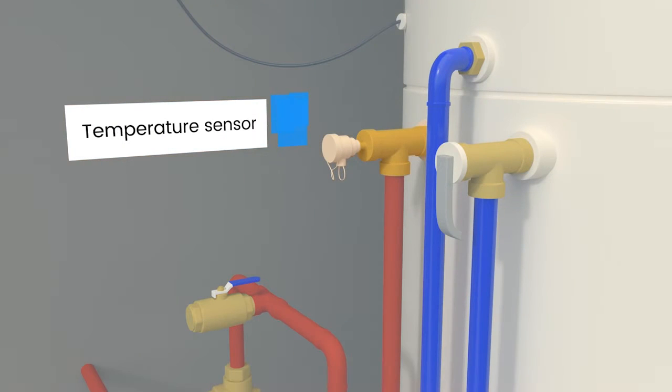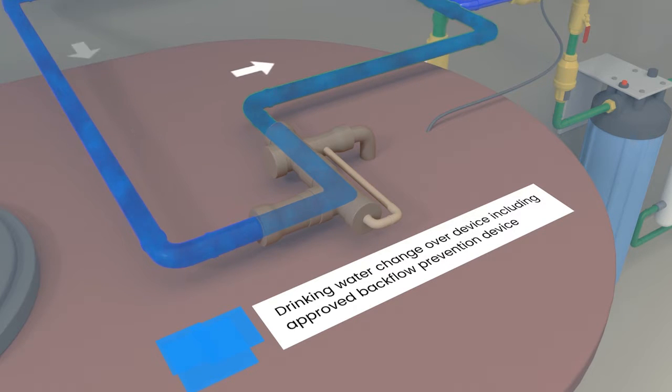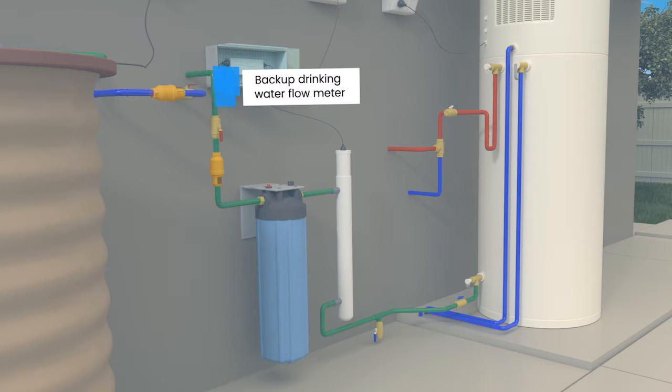The temperature sensor monitors that all the hot water within the heat pump unit has reached a temperature of 60 degrees. In the event that rainwater is not available, an automatic changeover device will substitute drinking water for rainwater to ensure a continuous hot water supply in your home. This device also prevents rainwater from entering the drinking water supply. There are two flow meters fitted to your rain-to-hot water system: on the supply line that provides backup drinking water and on the inlet to the hot water tank.